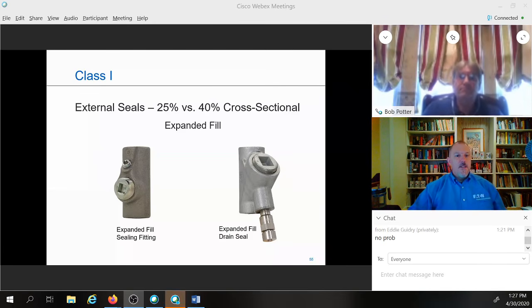Perfect. I got three more little questions here. We're at 127. So Mr. Facto asks, when do you need to split the jacket of a cable/cord in a seal to seal the individual conductors, and when are you permitted to leave the cable/cord jacket intact within the seal?